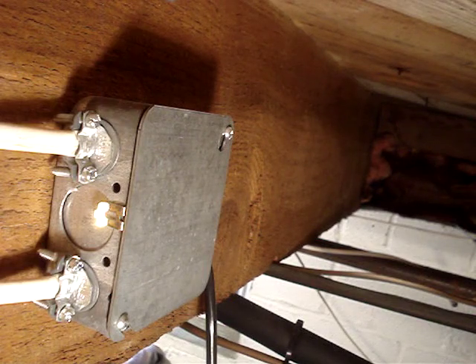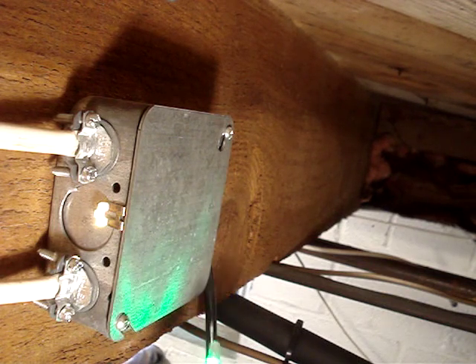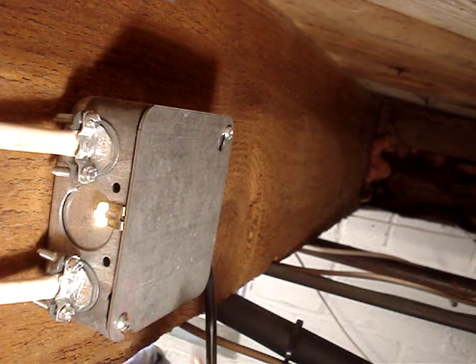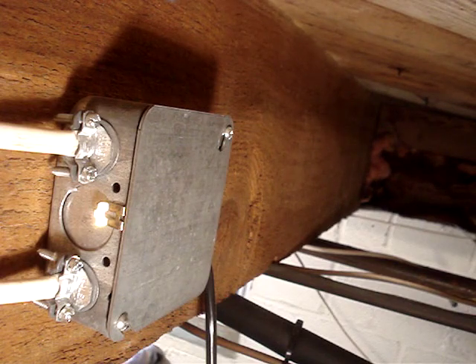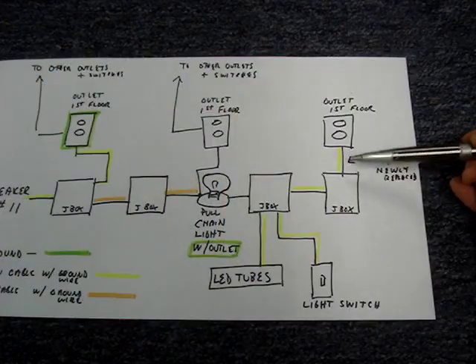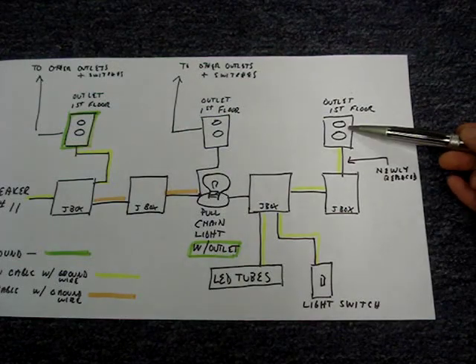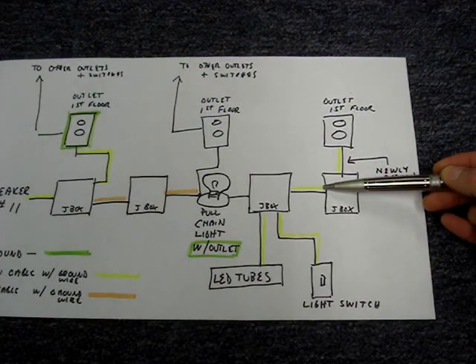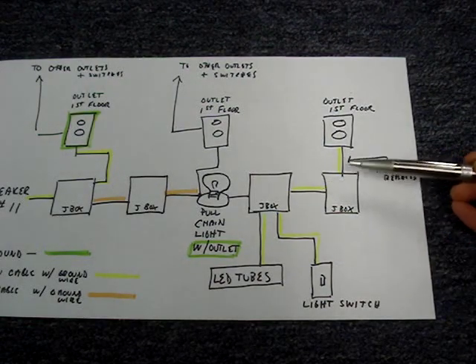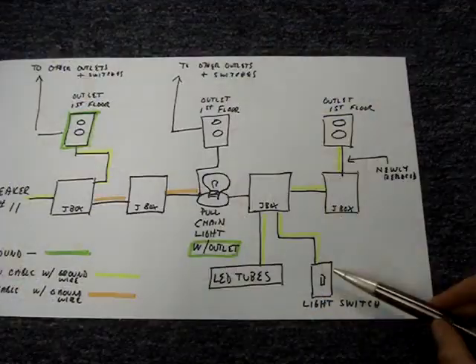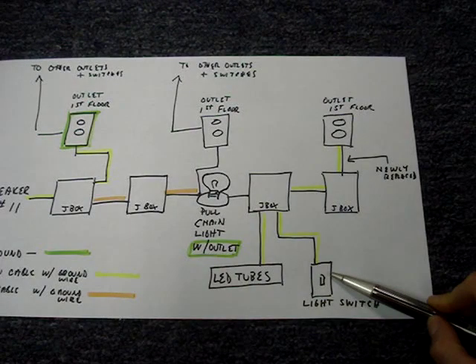During an earlier video, while troubleshooting a missing ground from a circuit, I discovered that the junction boxes on part of the circuit are energized. This video will show how to troubleshoot that problem. The wires that go from this junction box to the first floor outlet are disconnected. There's voltage on the ground wire that feeds into this junction box. This light switch box also has voltage on it.